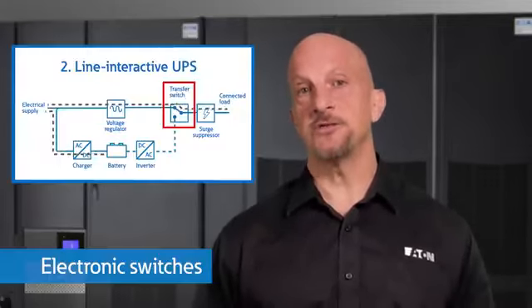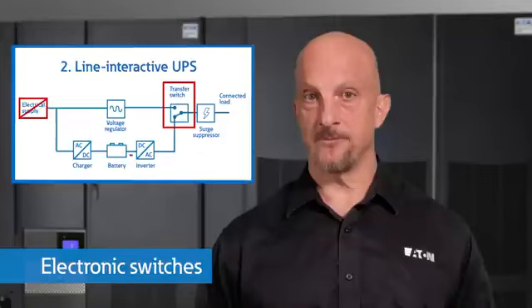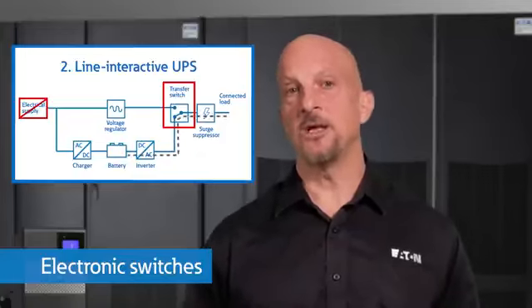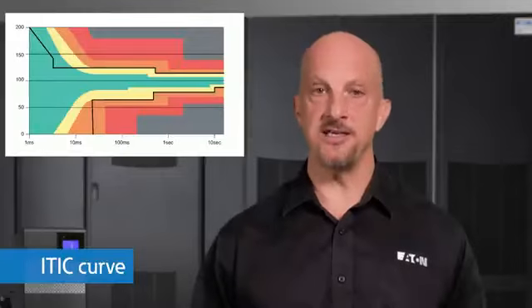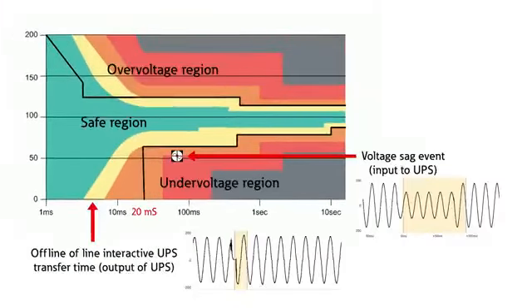So how can an offline or line interactive UPS turn off the power and turn on the battery so quickly that our computers don't drop out? The answer is the UPSs use electronic switches. The key for success, though, is that computer manufacturers follow design criteria called the ITIC curve, so the computer power supplies have enough ride-through to last a little more than 1 60 Hz electrical cycle, or about 20 milliseconds.